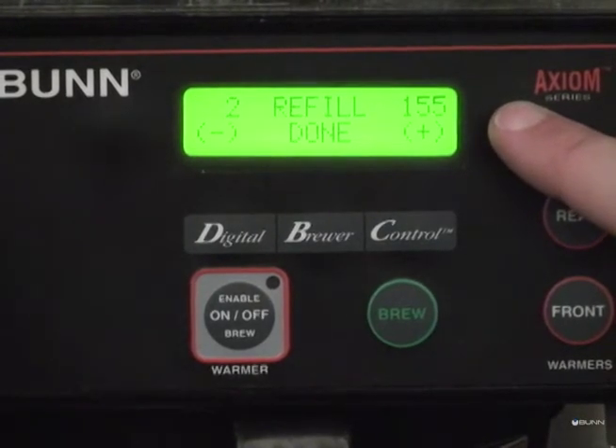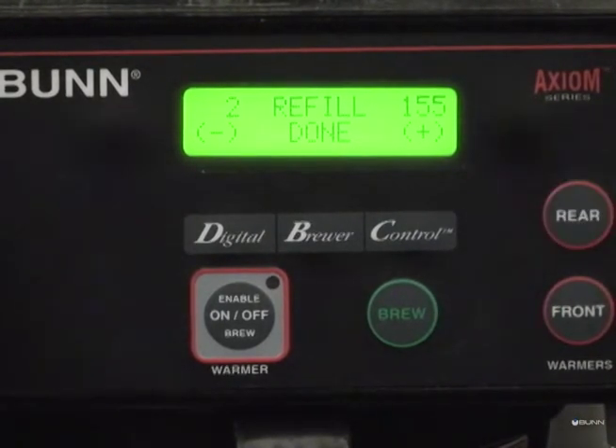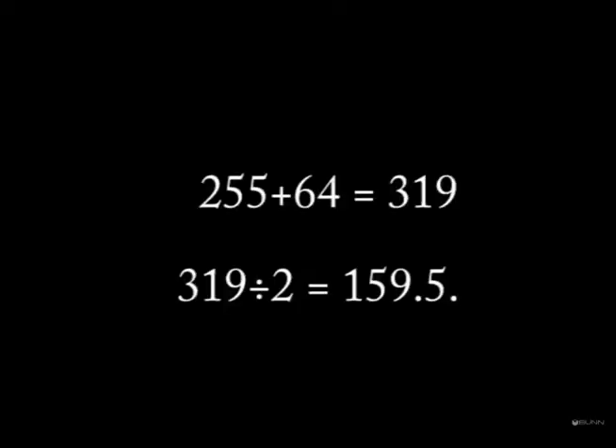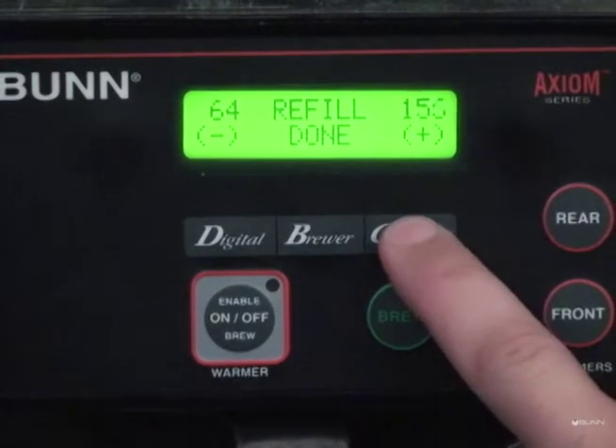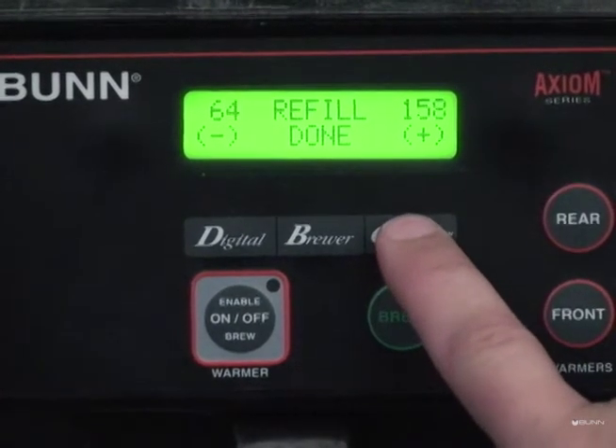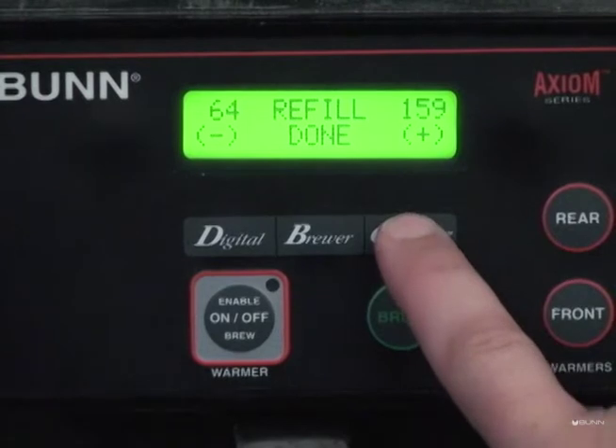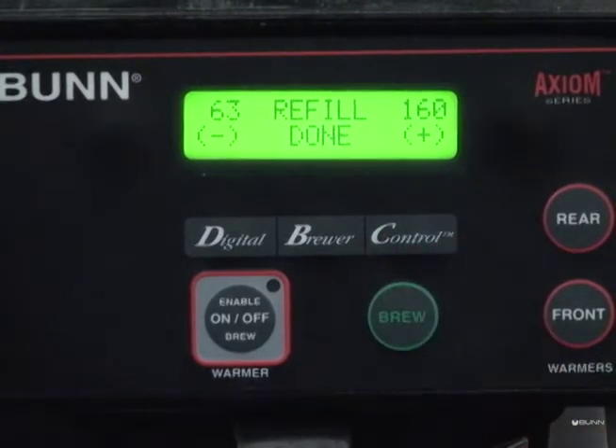Follow this procedure to figure out where to set the refill threshold number for less conductive water or low TDS, total dissolved solids. Take 255 plus 64 equals 319. Take 319 divided by 2 equals 159.5. You can round up to the nearest whole number. Always make sure refill threshold number on the right is larger than the number on the left when water is touching the long refill probe.